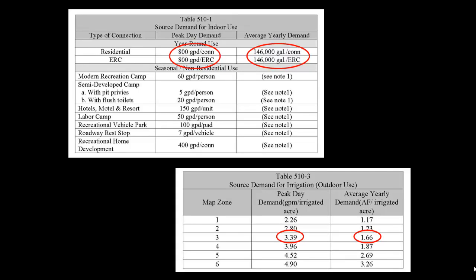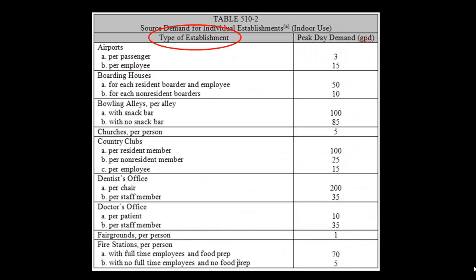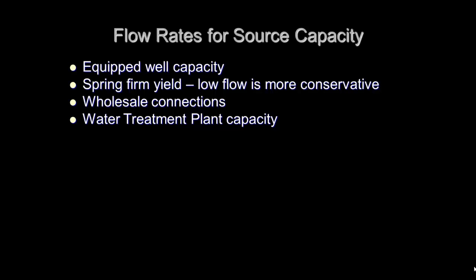These are copies of Tables 510-1 and 3 showing the minimum values for indoor and outdoor source demands. Table 510-2 lists demands for various types of establishments that may be associated with non-community water systems. This table includes many other establishment types not shown here. We often get questions on where to find the flow rates to use in the capacity calculations. To get these values, it may take some work and should be determined during the survey. For example, they may include the equipped well capacity for a well, yield of a spring, or low flow — which is more conservative and can be calculated with a stopwatch and a gallon bucket during the survey. Flow rates may also be based on a wholesale connection agreement or the capacity of a water treatment plant.